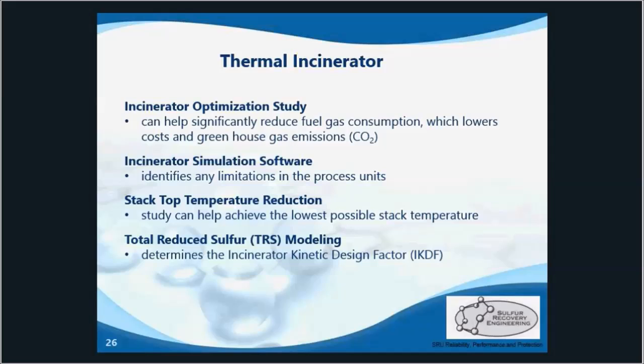These often produce significant savings on fuel gas consumption and greenhouse gas emissions. Our simulation modeling can determine capacity limitations, minimum achievable stack top temperature, and the incinerator kinetic design factor — that's the IKDF. That describes the relationship between the stack top temperature and the amount of total reduced sulfur species, TRS.